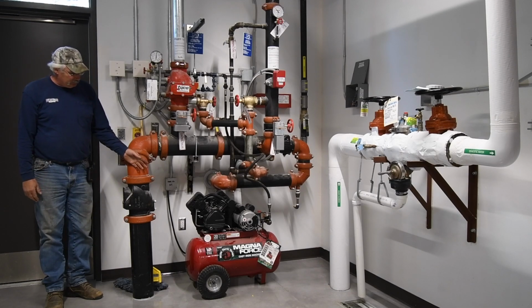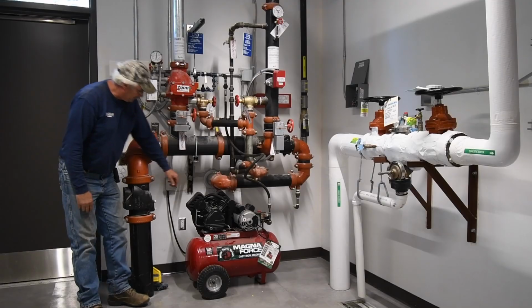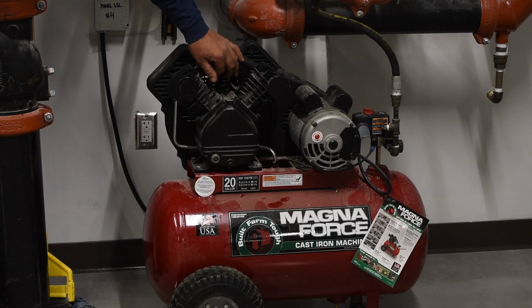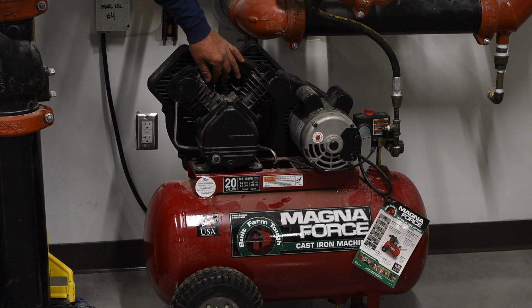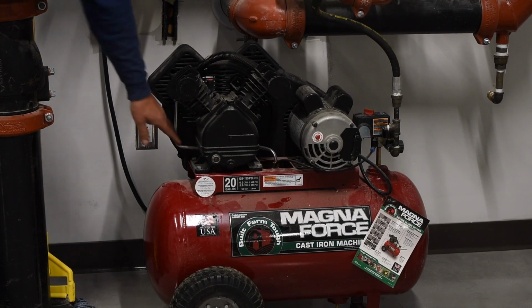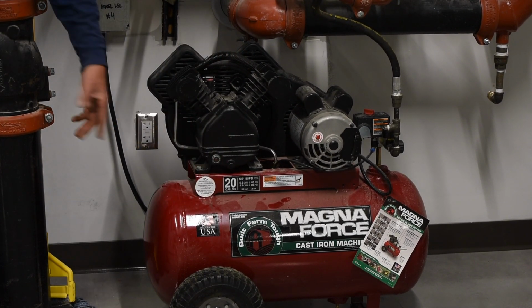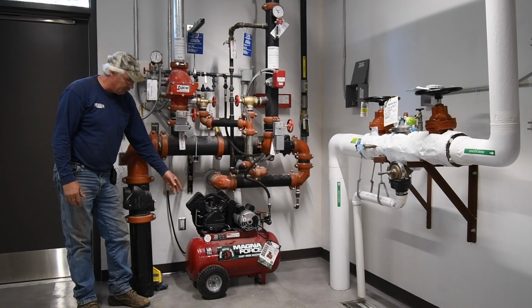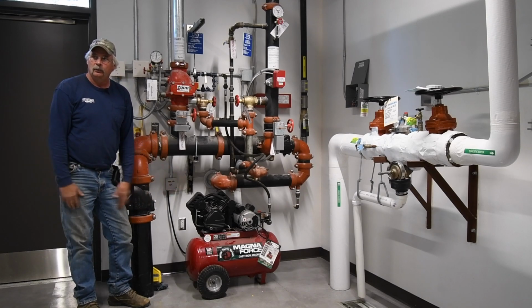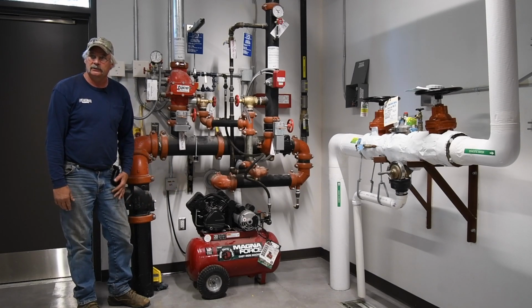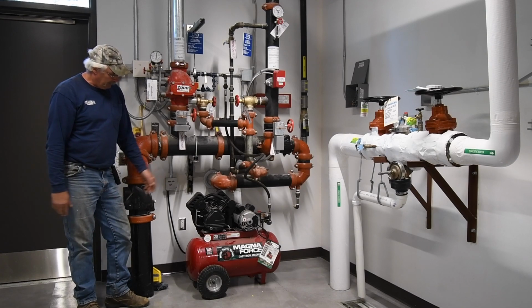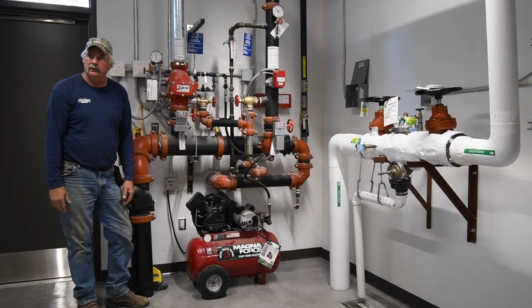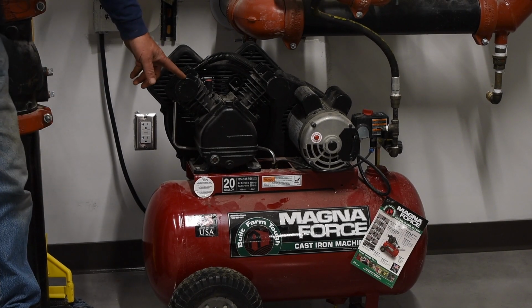One of the things on the air compressor, this is actually where you fill your oil here. If you need to add oil for some reason, if you want to change oil, there's a plug here on the bottom, right here. You know, you can shut the air compressor off, drain the oil, change oil. We do that on inspection once a year. It's air compressor oil, I believe it's a 20 weight oil. This is your air filter.